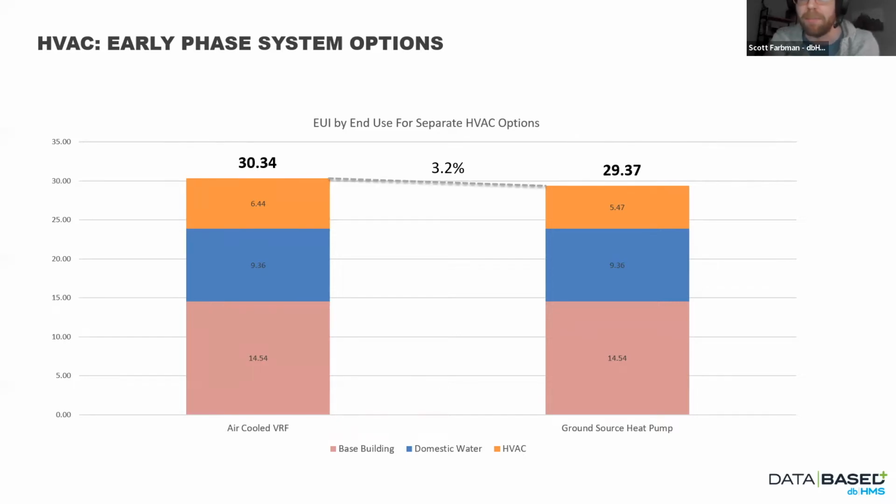When we really ran the numbers on our energy models, we found that on this building typology, especially on high performance buildings that have a lot of value in the thermal envelope, so heating and cooling loads are really minimized, the extra coefficient of performance, or COP, that you get from a geo-exchange loop on your heating and cooling systems, while it does increase it, pretty high 5+ range, the amount of energy you're spending to heat and cool the building is pretty minimal. Tom showed it on WUFI a little while ago. Space heating and cooling is really a small slice of the pie.